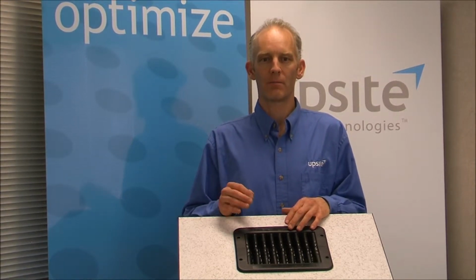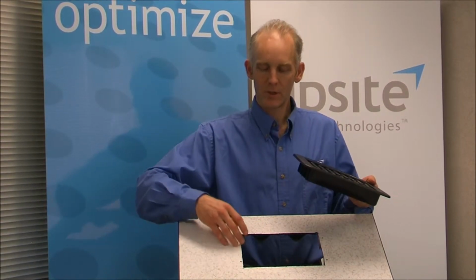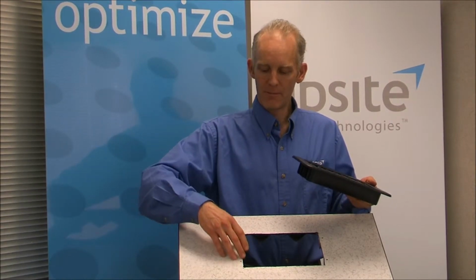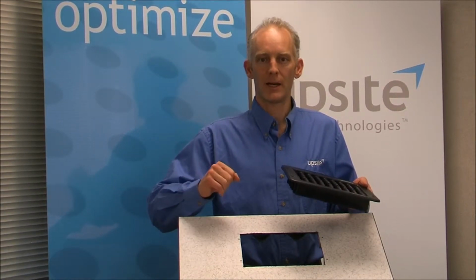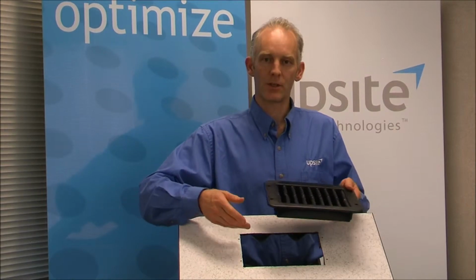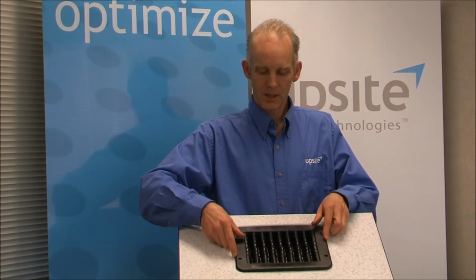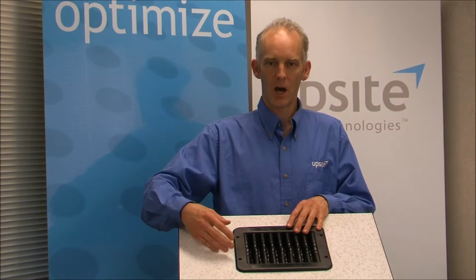The KoldLok Wave Grommet contains no loose or partially fastened parts, which can become separated or fall through the raised floor. The KoldLok Wave Grommets satisfy NFPA 75, Section 5-4.4 requirement for self-dressing of raw metal edges. When cutting a hole in a raised floor tile, the raw metal edges are required by code to be dressed so that they don't cause chafing of cables. The grommet installed in a hole automatically dresses those holes.